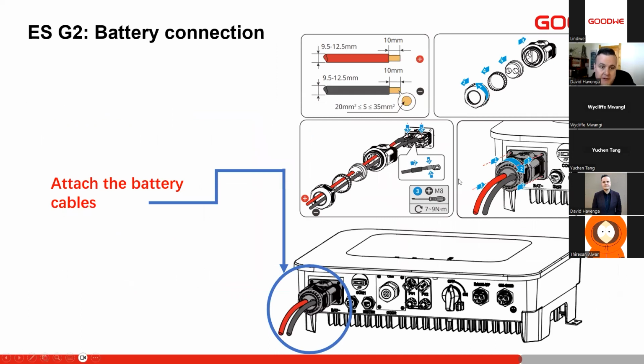The next is our battery connection. With our battery connection, we have the cover here as well as the lugs included. It's always good to make sure that you use a proper crimping tool to crimp these and the correct size cables. So you'll see we recommend a 20 to 35 millimeter cable. So 20 mil if you're using a 3 kilowatt device, 35 mil if you're using a 5 or a 6 kilowatt device. These are the recommendations, especially if you are installing a bigger battery bank. And this is all in the user manual.